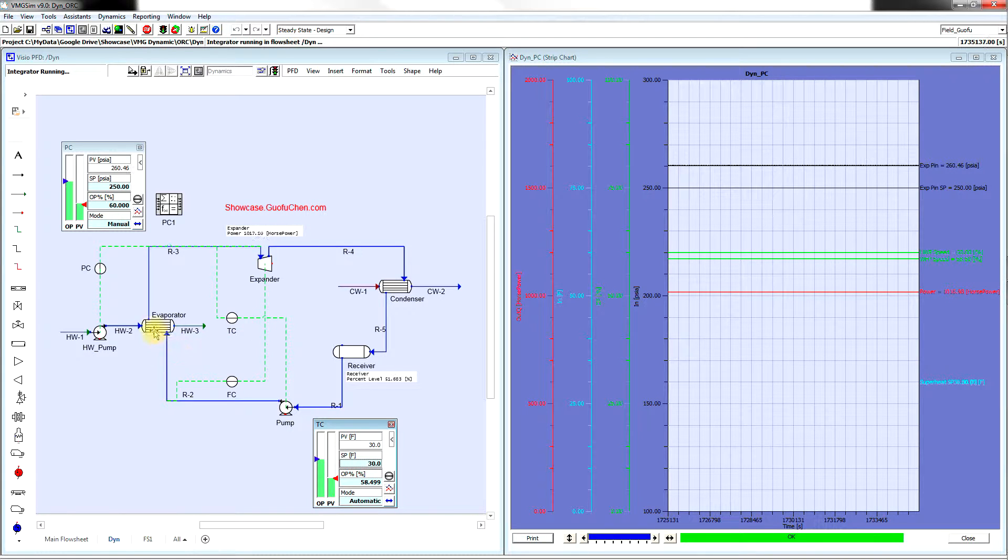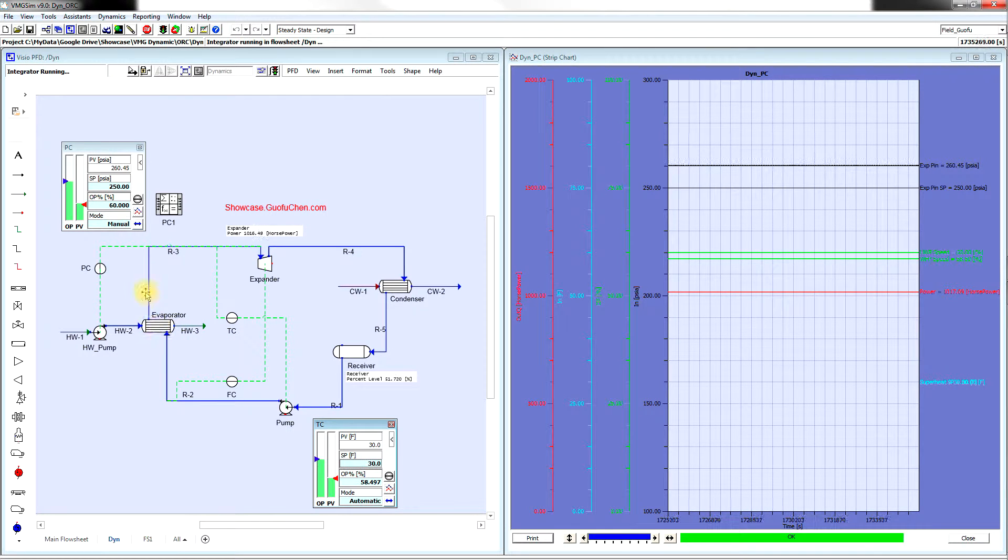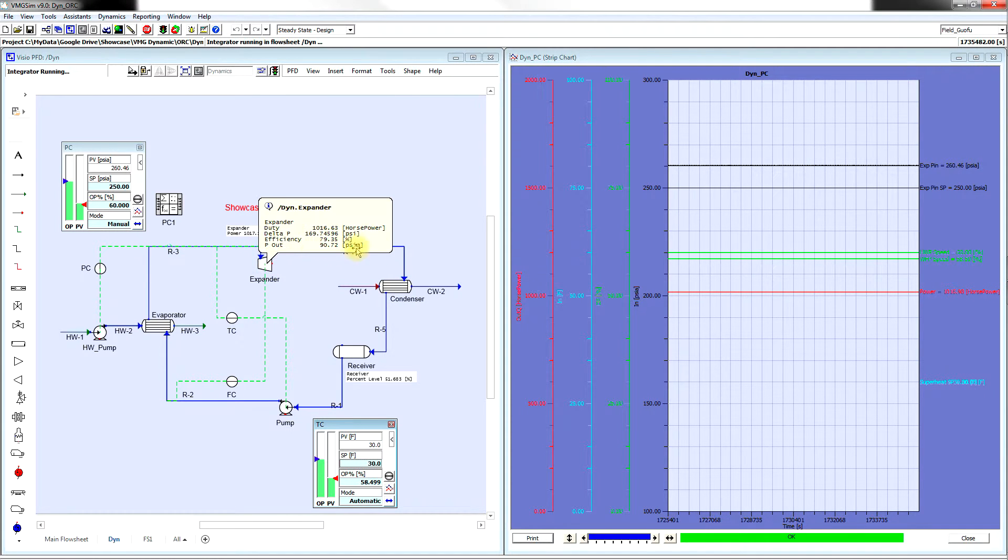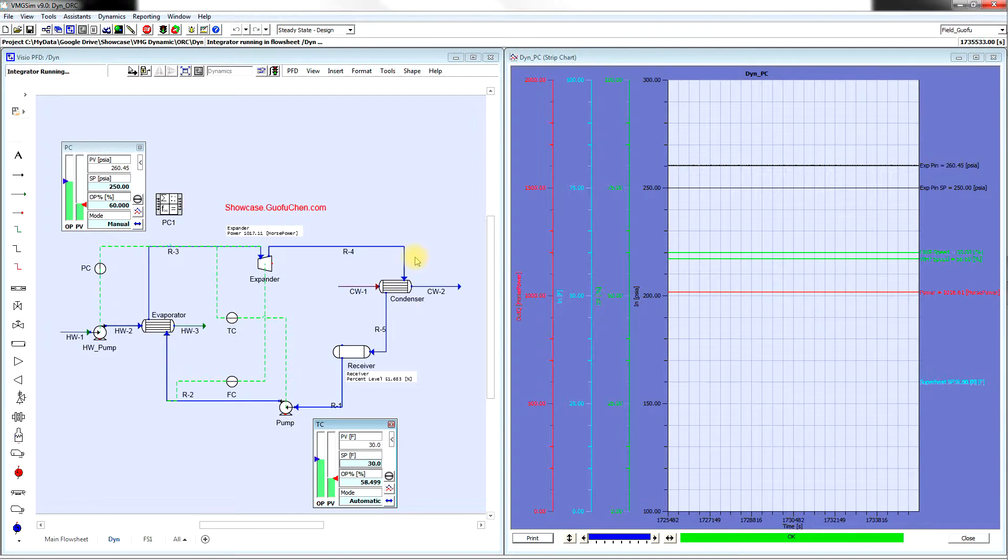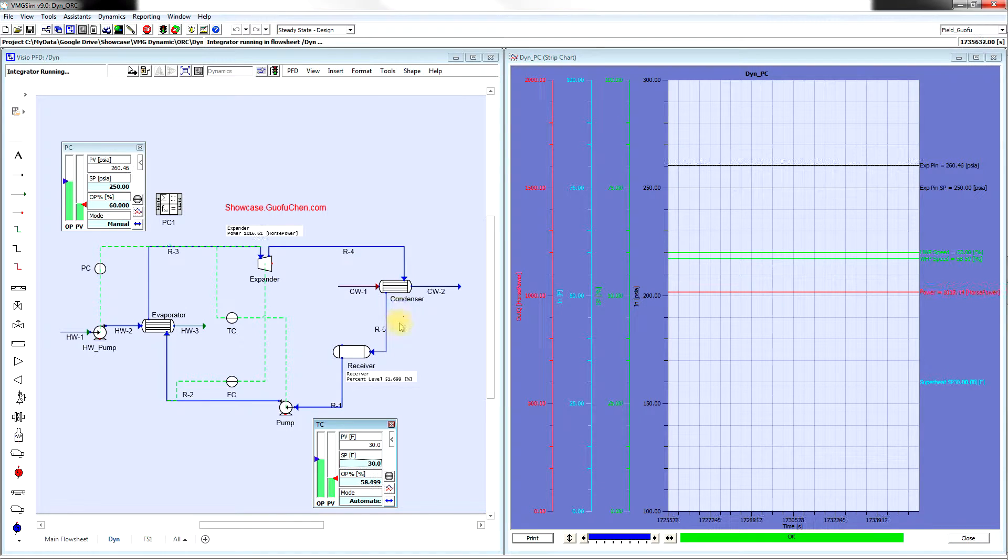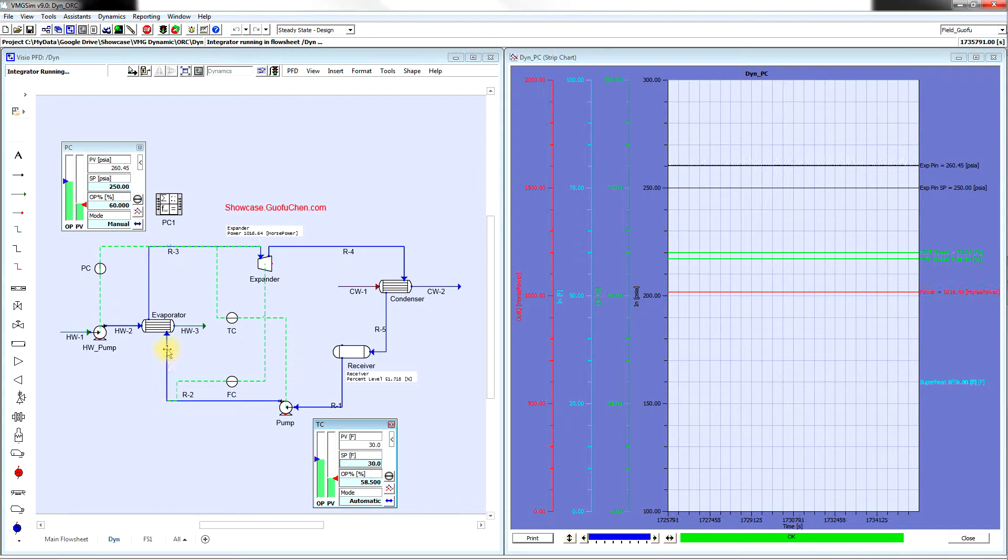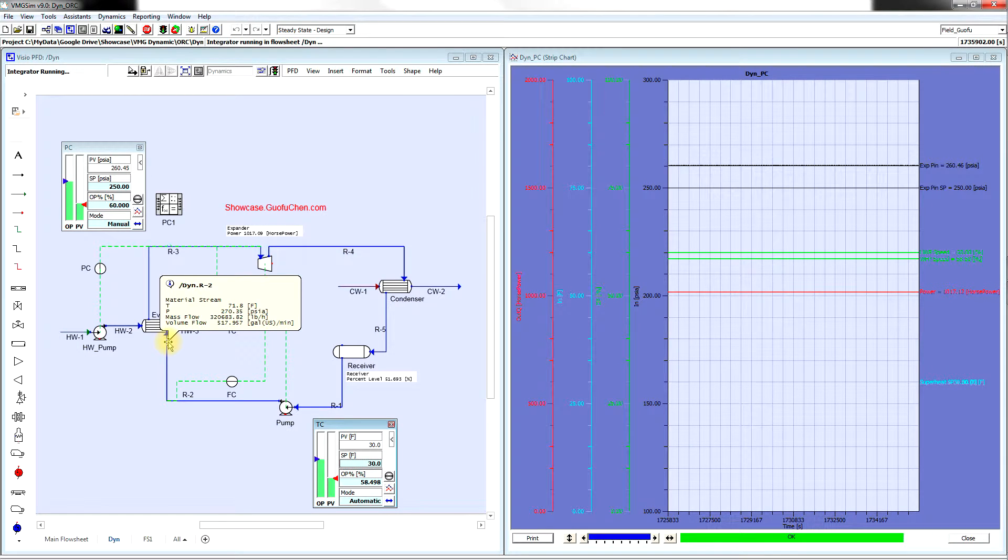The hot geothermal water boils the refrigerant into vapor to drive the expander to produce electricity. After it is fully condensed in the condenser, it is sent to the receiver, and then it is pumped back to the evaporator to complete the closed refrigeration loop.